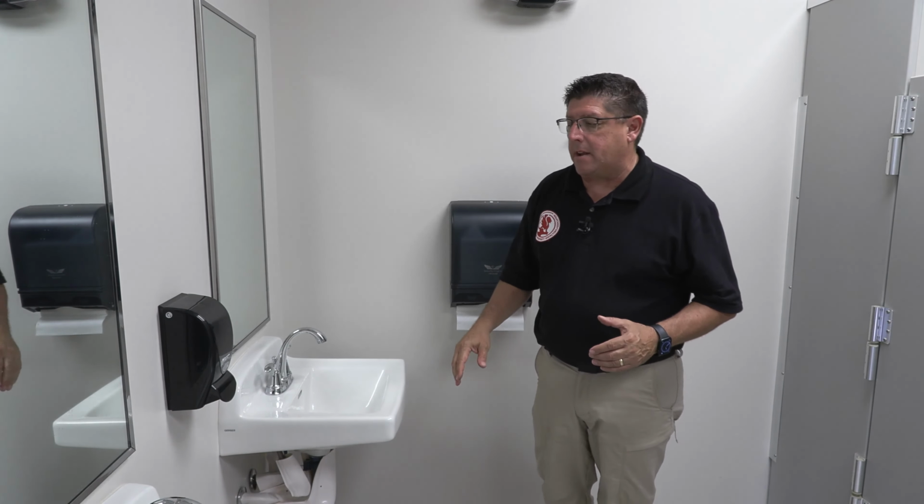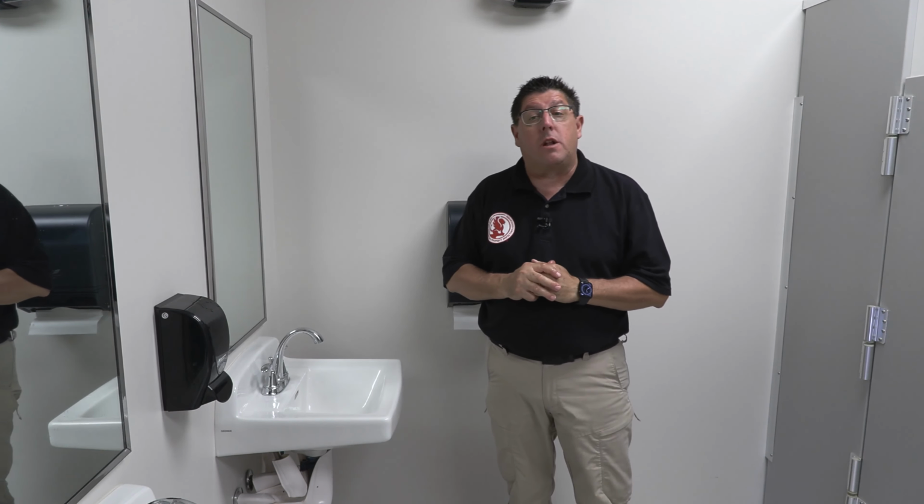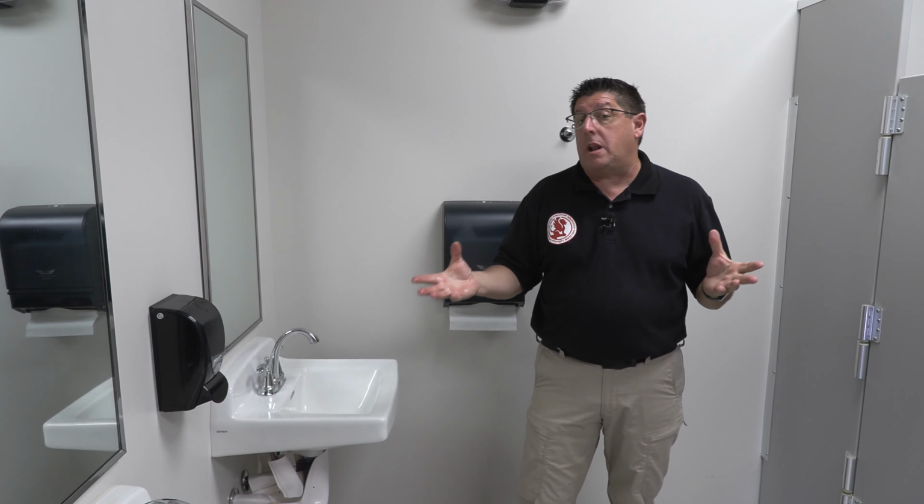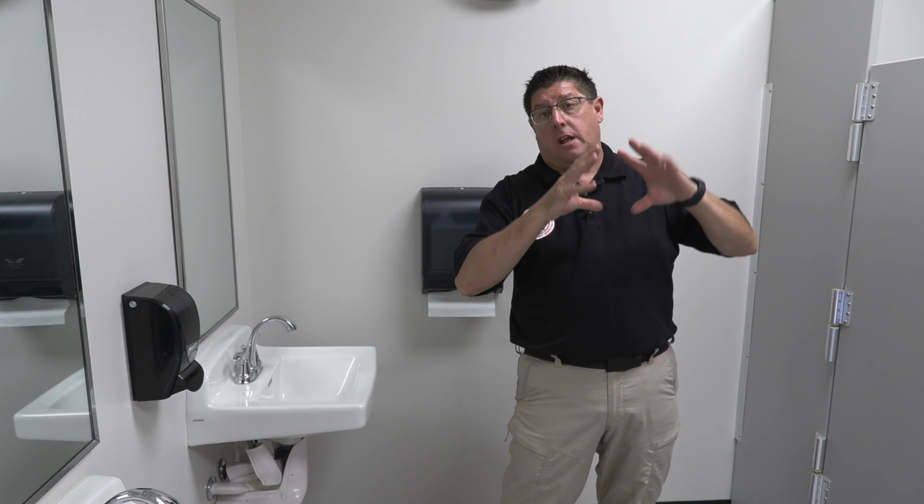I verify that. Check out any other dispensers we might have. Look at the mirrors to make sure they're not broken. All restrooms should have ventilation. The ventilation is either automatic or permanently on. In this particular case, this ventilation is operated by a motion sensor, and it operates for a specific period of time, and this is exiting up through a trunk system on the roof.